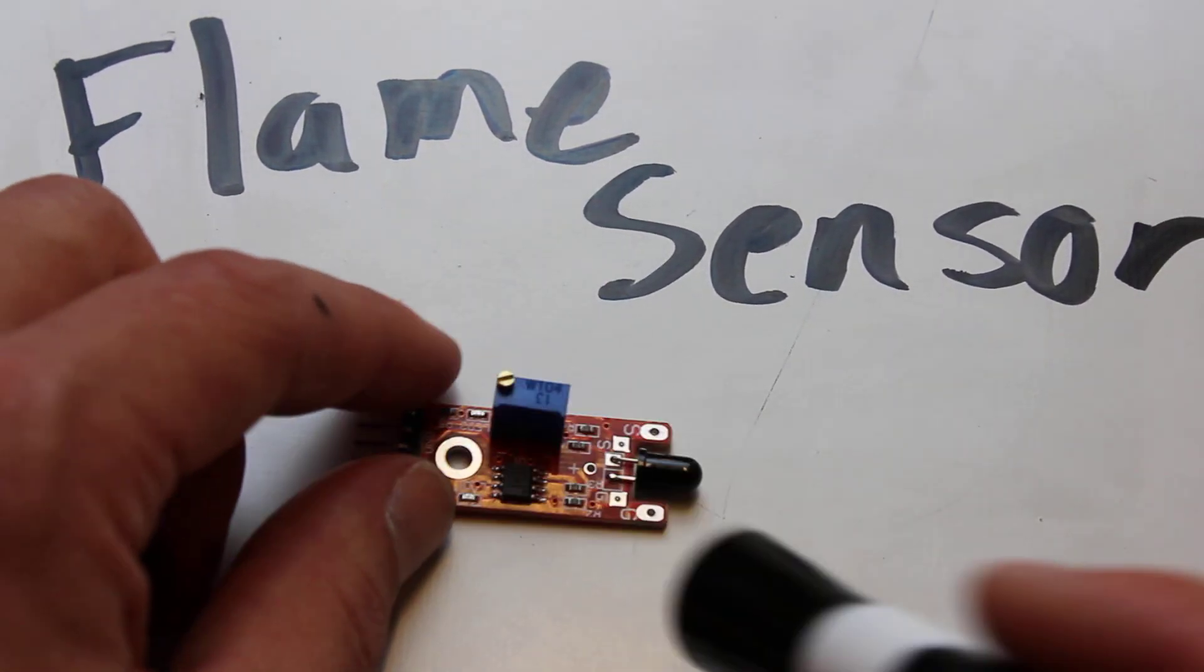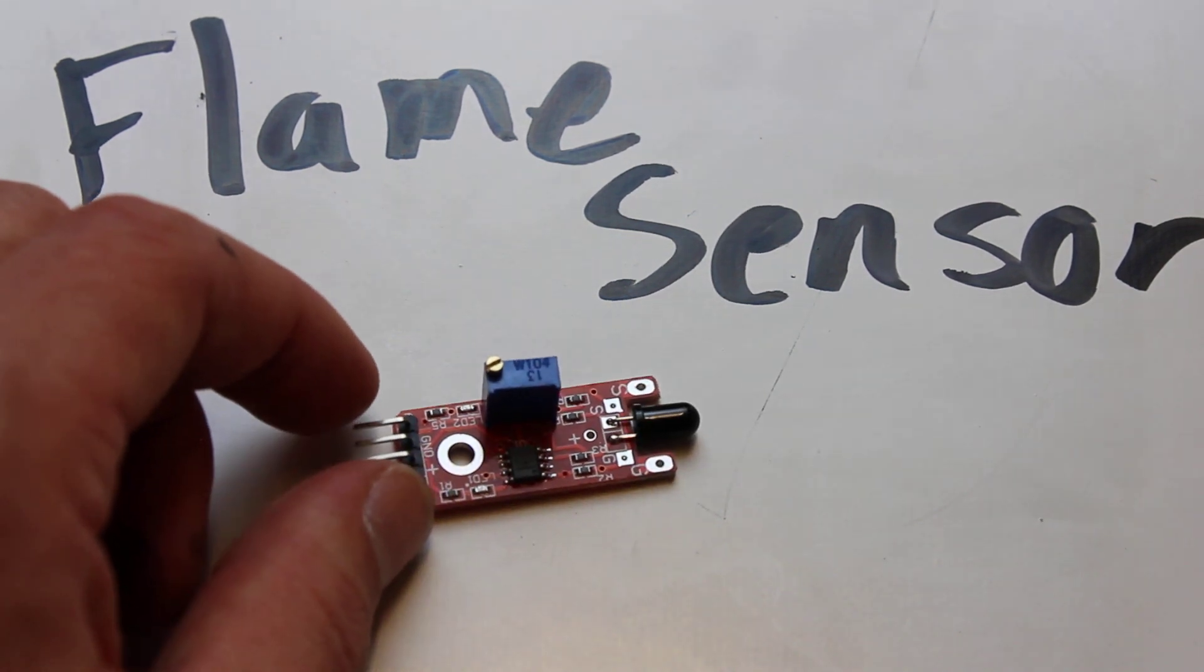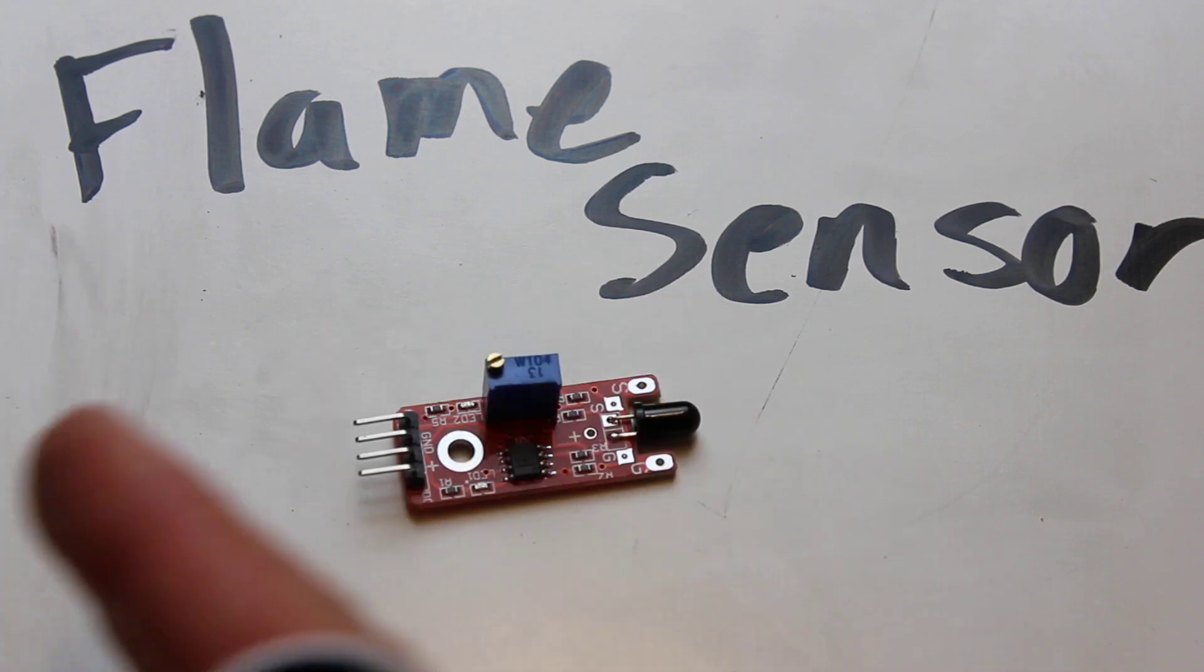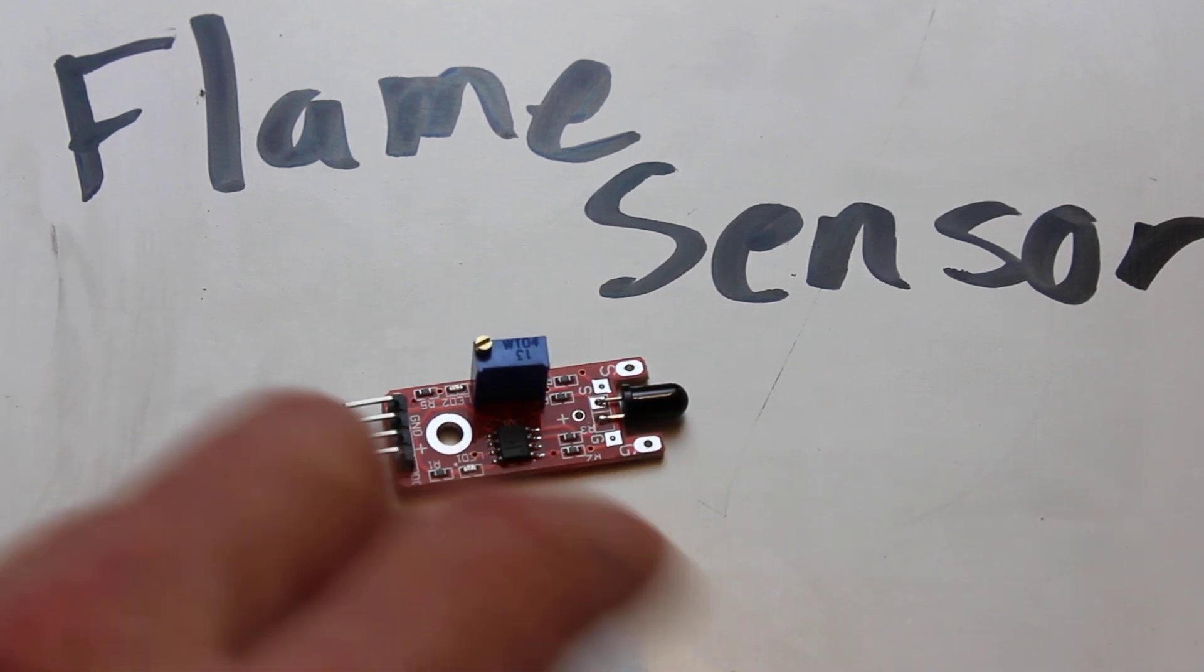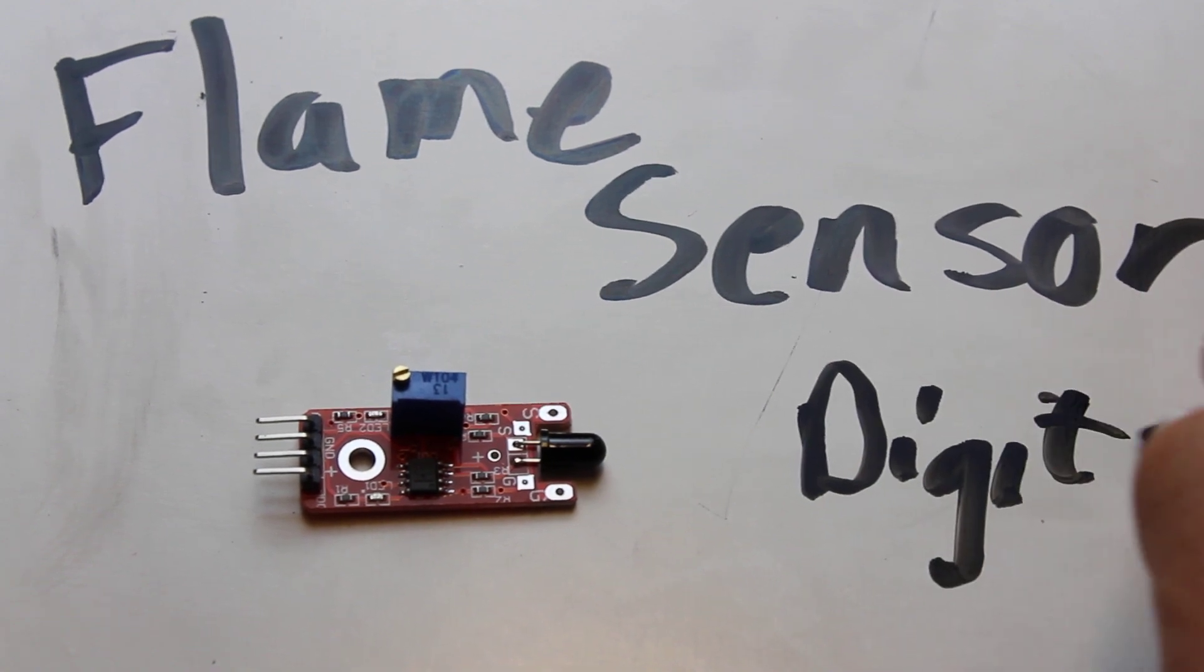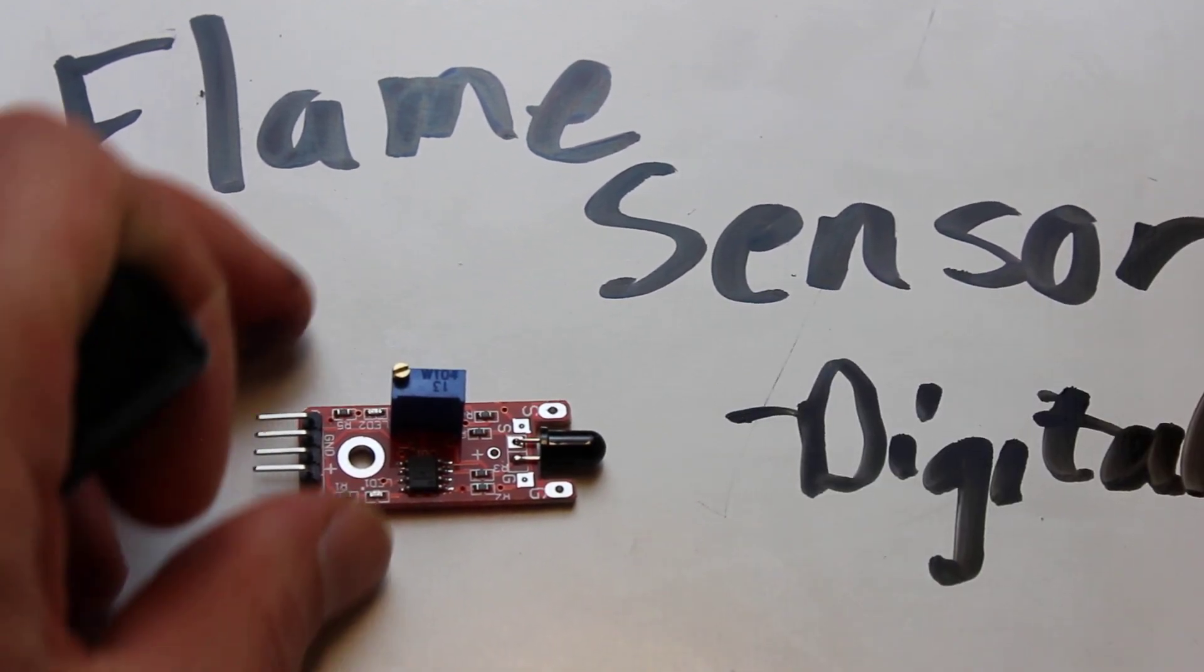You do have to trim the data that comes out of it a lot because it's a very narrow range where it's going from no fire to fire. So generally we recommend you use this as a digital signal, a digital output.